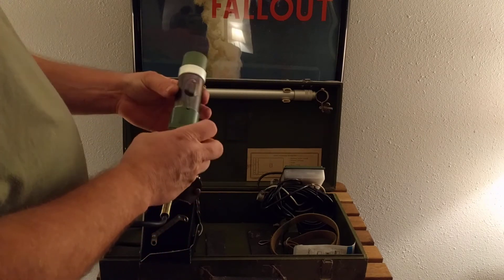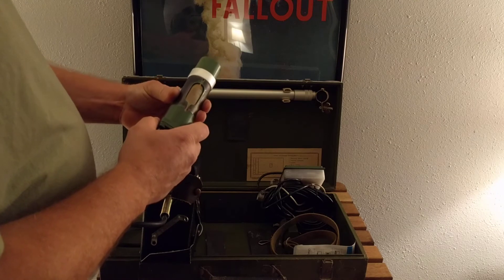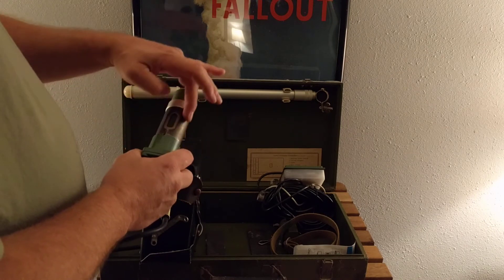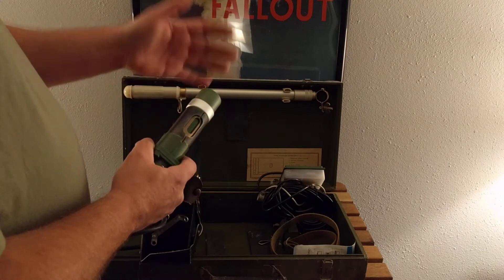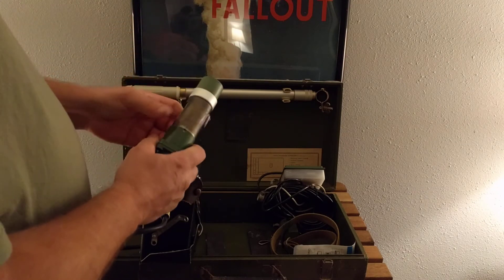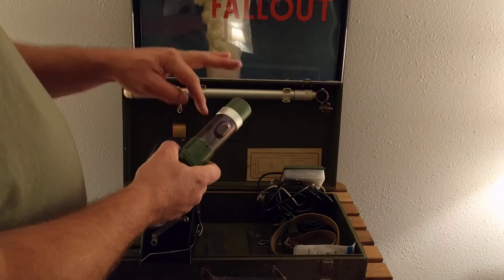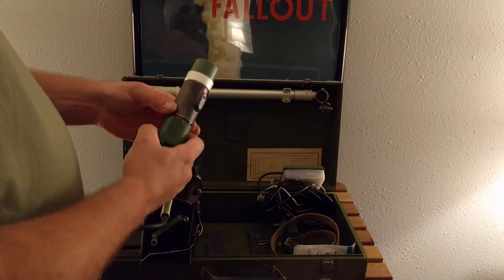This here is your probe. Pull it up, lock it in place, and eventually you come to this: this metal serves as the beta shield. This will allow betas through, but you're really not going to measure alphas. If you orient it this way, it measures gamma. If you have it set up facing the check source — which is strontium-90/yttrium-90 — it's going to be facing into the beta shield. It's an almost pure beta emitter, and that's used to test the unit.